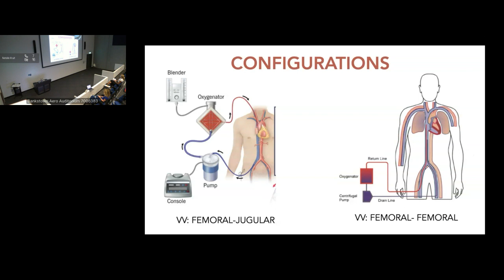That drains blood under negative pressure into the pump. Now, we have no access ports on this side of the pump because if a tap were to come loose, you would get an air embolism or entrain air and stop the pump. Blood is then sucked into the pump, so it's a centrifugal pump, and then it pushes blood out under pressure.